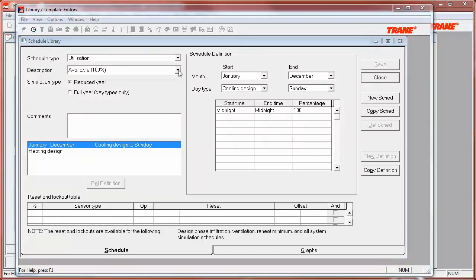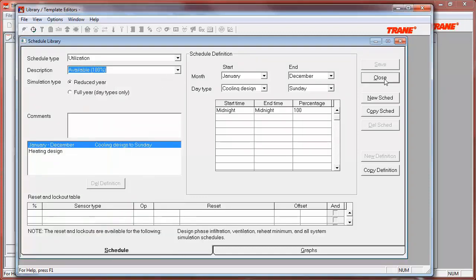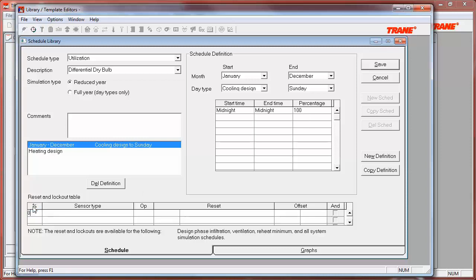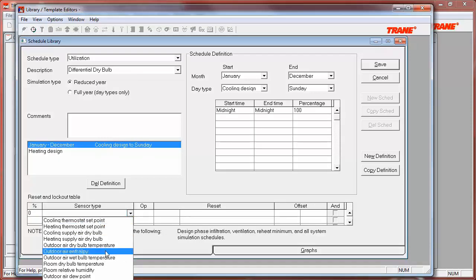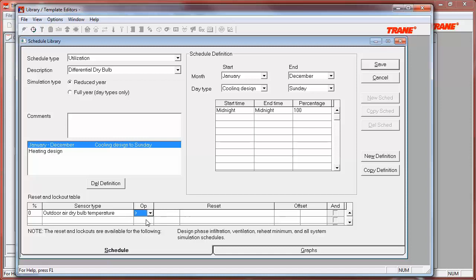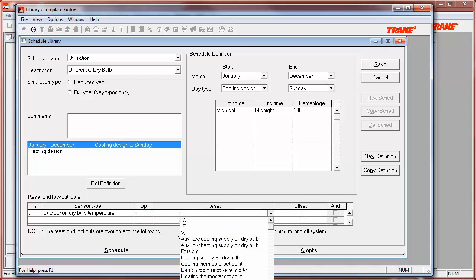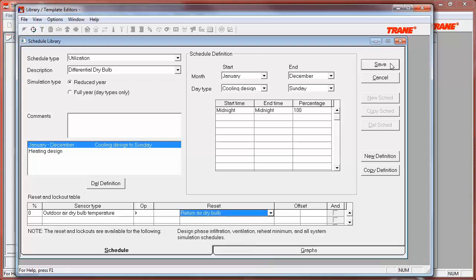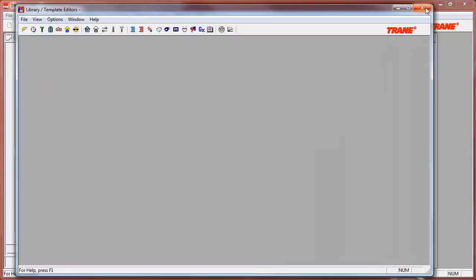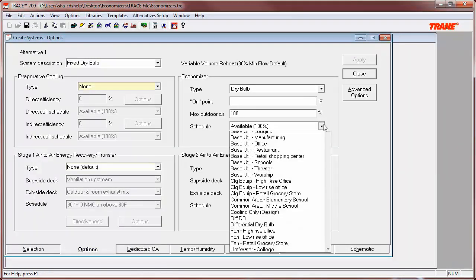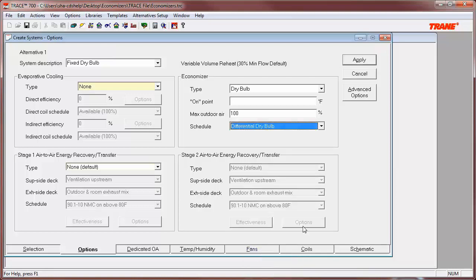The simplest way to do this is to select the available 100% schedule, click the copy button, give this new schedule a name, and apply the lockout in the reset and lockout table. Since the default operation is 100%, the lockout will be set to 0% operation when the outside air temperature is greater than the return air dry bulb. Click the save button, then go back to your project file and apply the schedule in the economizer section.